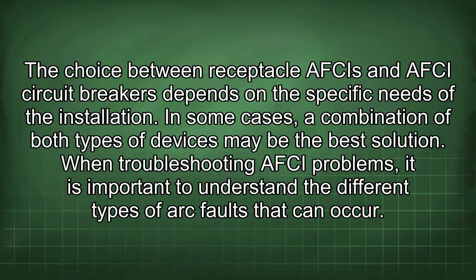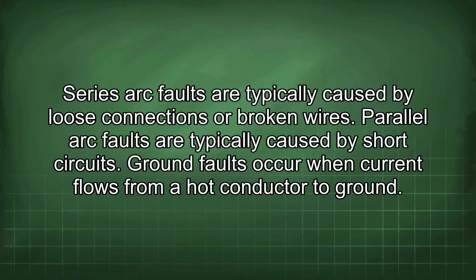When troubleshooting AFCI problems, it is important to understand the different types of arc faults that can occur. Series arc faults are typically caused by loose connections or broken wires. Parallel arc faults are typically caused by short circuits. Ground faults occur when current flows from a hot conductor to ground.